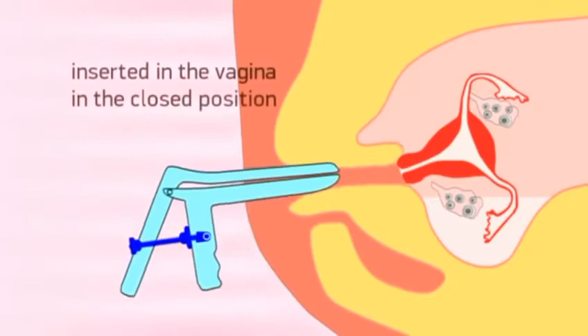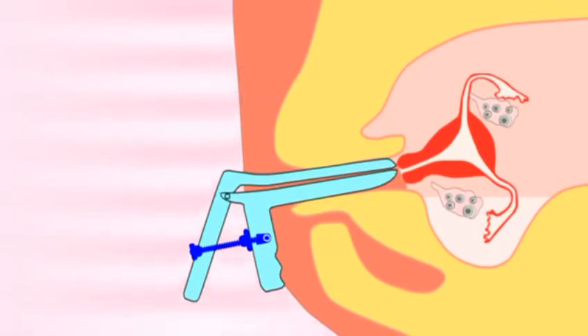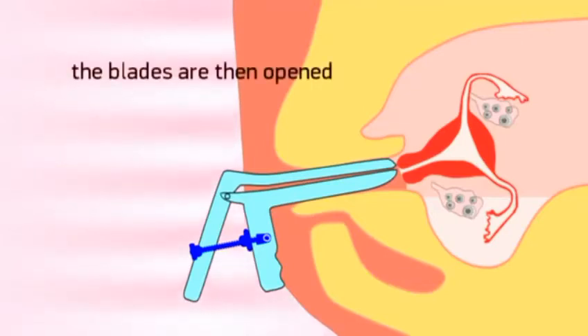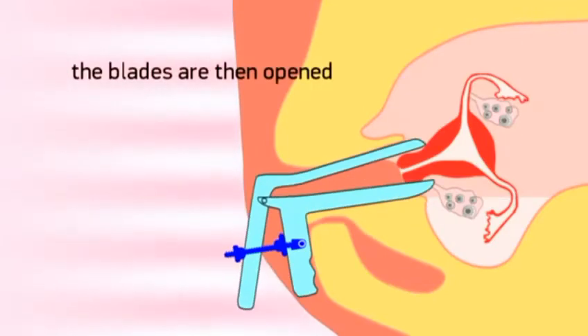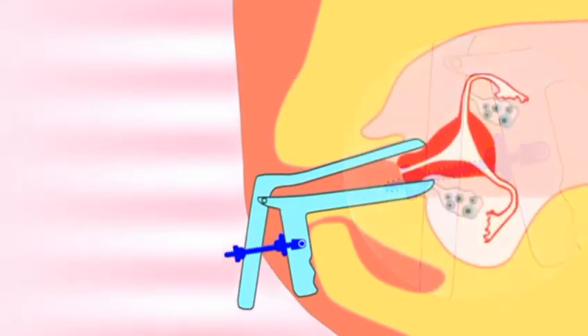The Procedure. The DNB Cervical Clamp is inserted in the vagina in the closed position, with the inner nut being close to the posterior blade handle. The blades of the DNB Cervical Clamp are then opened by turning the outer nut clockwise, thereby allowing good visibility of the cervix.